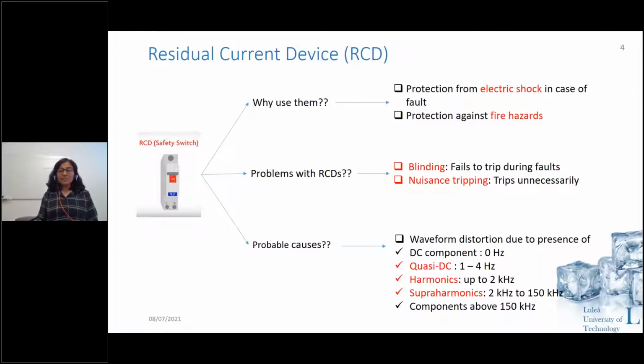One is blinding, that is, the RCD fails to trip during a fault, which is very severe, because if there is a fault condition and the RCD doesn't see it and does not trip, then if someone is touching a live part, the person will surely face shock. Another is nuisance tripping, which means the RCD trips unnecessarily. I mean, even when there is no fault, it trips. So that is another problem with RCD.